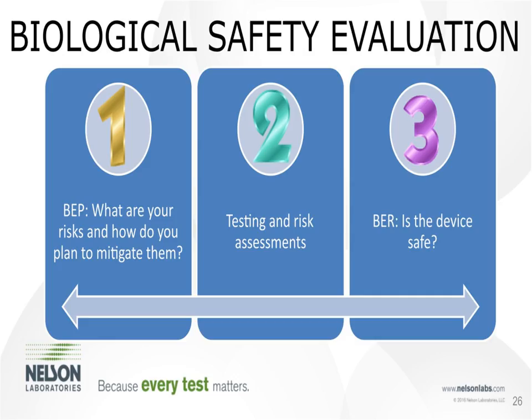Dr. Campbell pointed out some of the price and time benefits of doing extractable and leachable testing with the risk assessment versus just doing all of the animal testing. And then today, part three, following up with your biological evaluation report, identifying if your device is safe. Do not leave room for assumptions for the reviewers because they simply won't make them. It will just create work on the back end for you. So make those justifications and then support that biological safety through to the end.